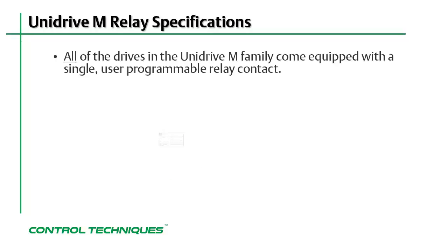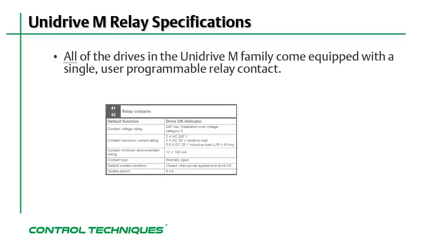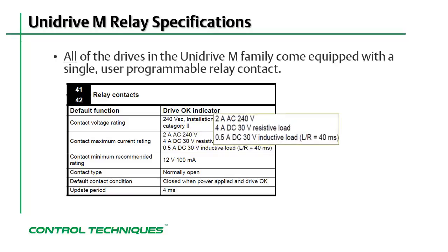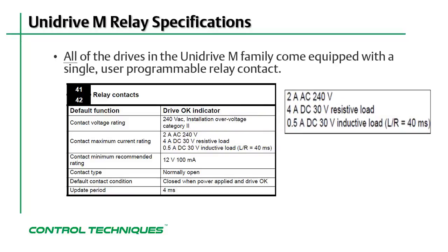The specifications for the relay contact are shown here. The range of input voltage that may be used on the relay contact is from 12 volts DC at 100 milliamps up to 240 volts AC at 2 amps. Let's take a closer look at the maximum current rating.